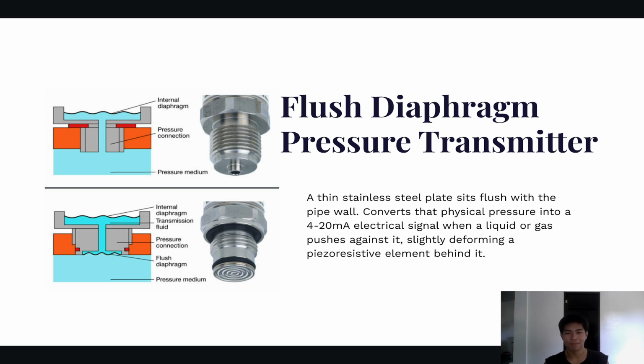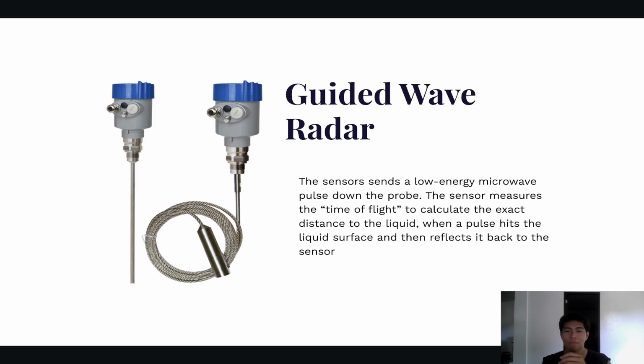Next is the guided wave radar. The sensor sends a low-energy microwave pulse down the probe. The sensor measures the time of flight to calculate the exact distance to the liquid when the pulse hits the liquid surface and reflects back to the sensor. The guided wave radar is placed vertically on top of the main storage tank, where the probe is let down, making contact with the liquid beverage inside.